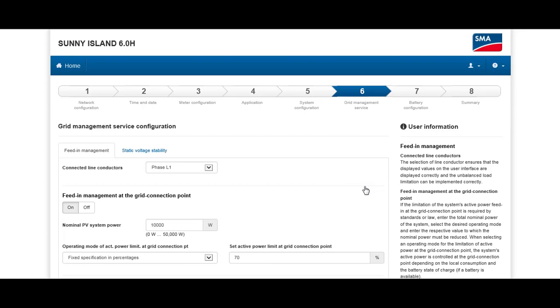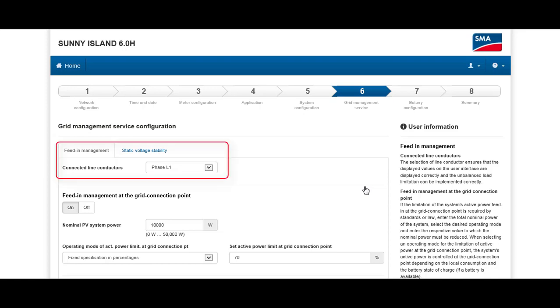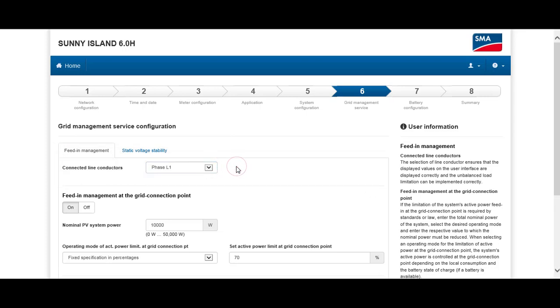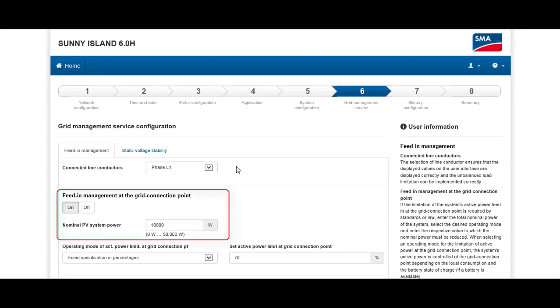Depending on the country in which the Sunny Island is used, different grid requirements affect the storage system as well as the PV system, which can also be configured in this step. First, choose which grid phase the Sunny Island has been connected to. In our case, we've connected it to phase one, so we don't need to change the default settings. You also have the option to turn the limitation of PV output power on or off.